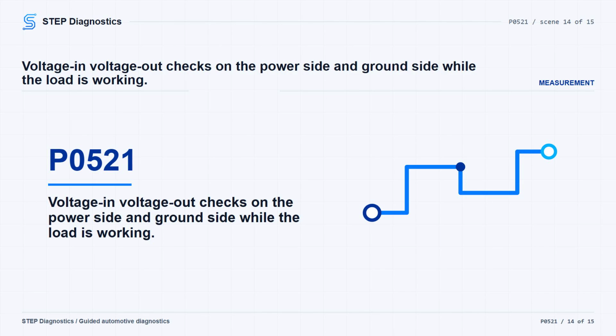For voltage in voltage out testing, put the negative meter lead to ground or battery negative, then measure the power side and ground side of the load while the circuit is operating. The power side should be within 0.5 volts of battery voltage. The ground side should be greater than 0 volts but less than 0.5 volts. A reading of 0 volts or source voltage indicates an open circuit.